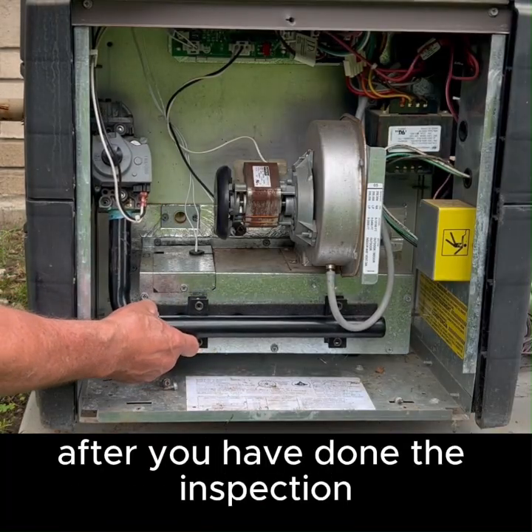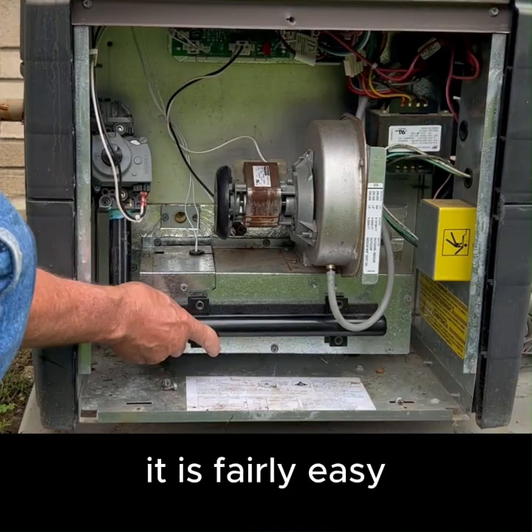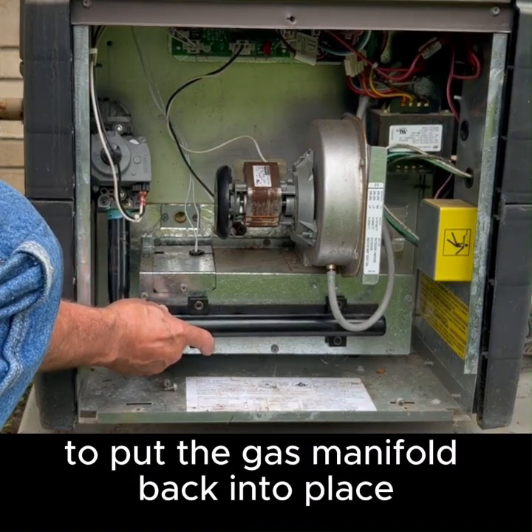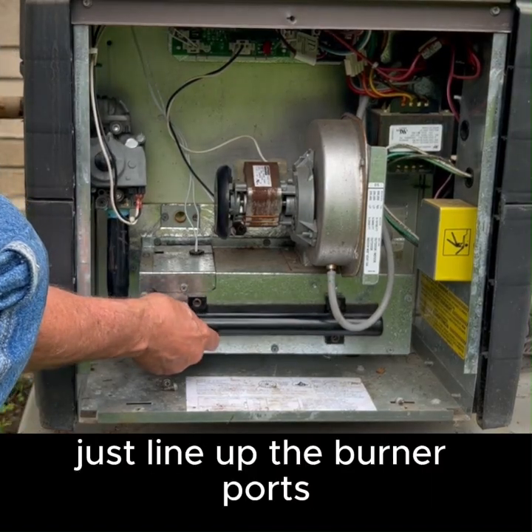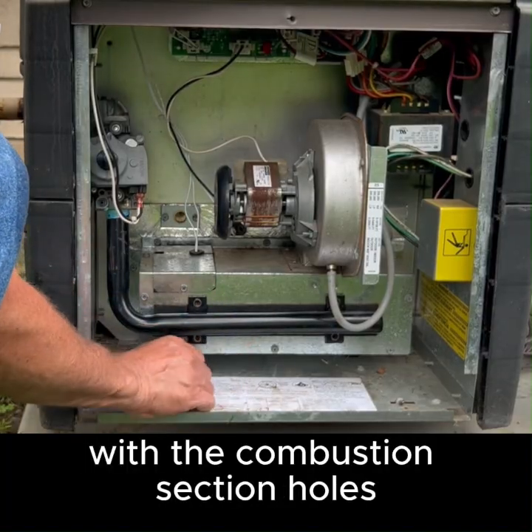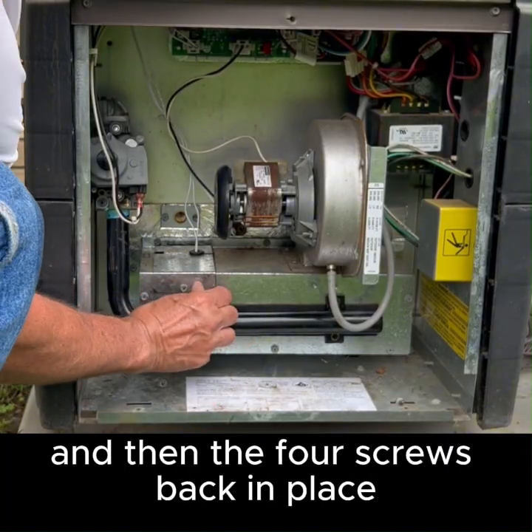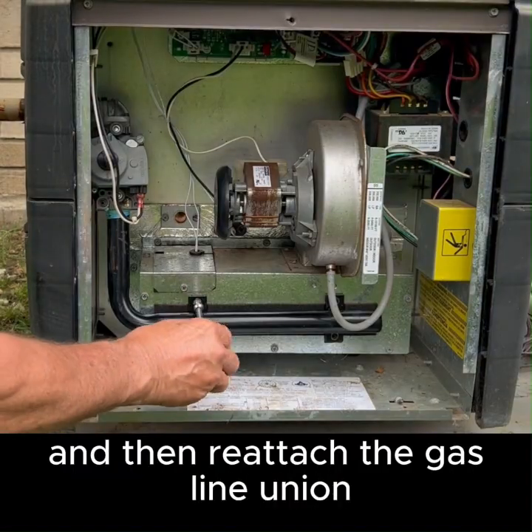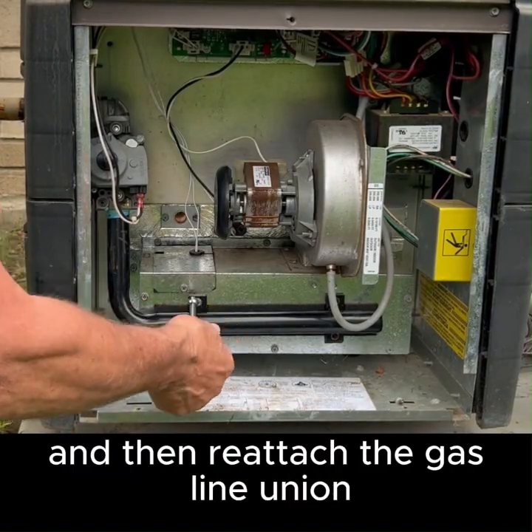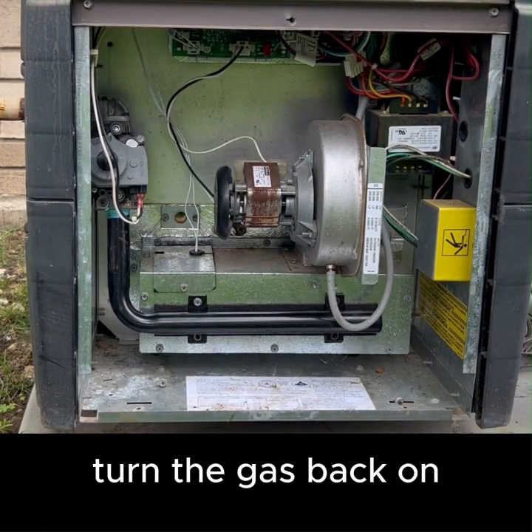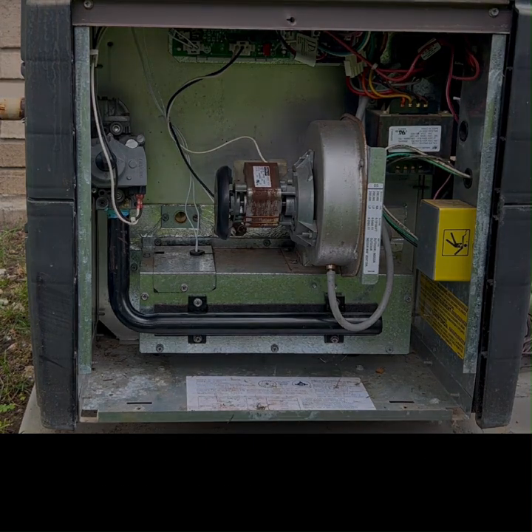After you have done the inspection and everything looks good, it is fairly easy to put the gas manifold back into place. Just line up the burner ports with the combustion section holes, and then put the 4 screws back in place, and then reattach the gas line union, and then of course turn the gas back on. It's as simple as that.